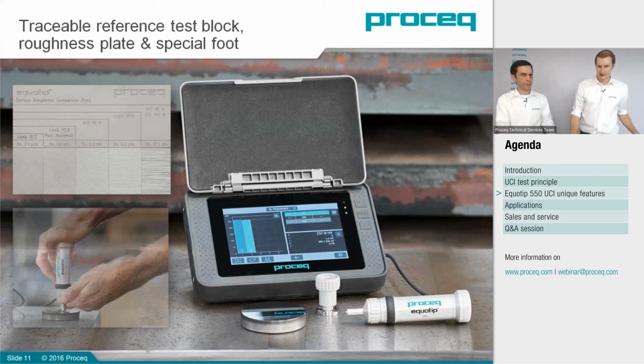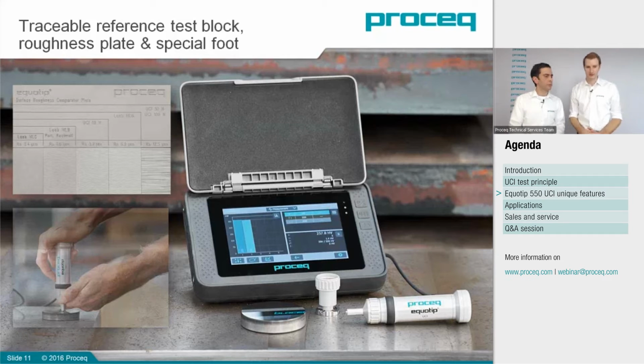The second standard accessory shipped with every unit is the roughness comparator plate. This is needed to verify you have proper surface preparation. As with all hardness testing methods, for UCI you must make sure the surface roughness is good enough, otherwise results could show high distortion or be completely wrong. With our comparator plate, you can easily determine if the roughness is good enough or if you need to do some surface preparation.